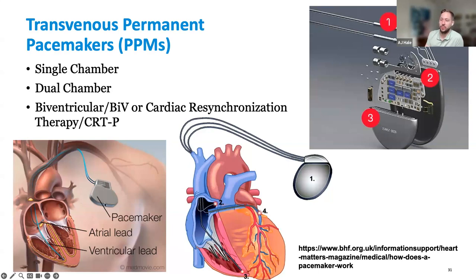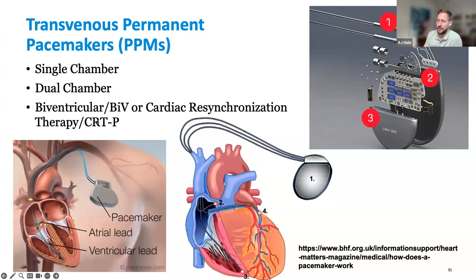There are new types and placements we'll discuss down the road, like left bundle and His bundle, which has kind of fallen out of popularity but is still in circulation. We also have biventricular or BIV pacemakers — cardiac resynchronization therapy, CRTP devices. If you hear someone say biventricular, CRTD, or CRTP, they mean the same thing. There will be three leads: one in the atrium, one in the ventricle, and one going through the coronary sinus to pace semi-epicardially. You can also pace externally through epicardial leads.